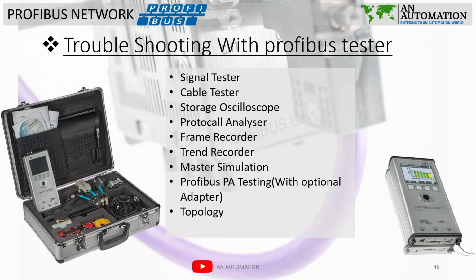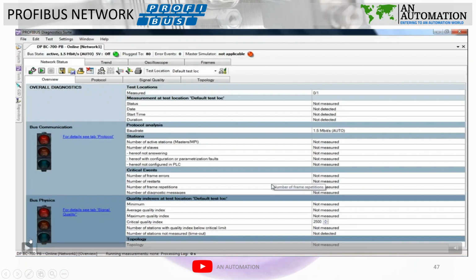So this is the most commonly used industrial tool to rectify or diagnose a Profibus network. This is a Profibus tester, by which we can do signal tests, cable tests, storage oscilloscope, protocol analyzer, frame recorder, trend recorder, master simulation, Profibus PA testing, and with an optional adapter, topology. How we will use this system, we'll see in the next video. So here is the video.